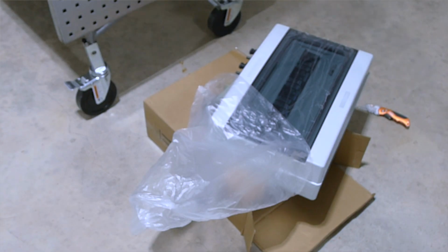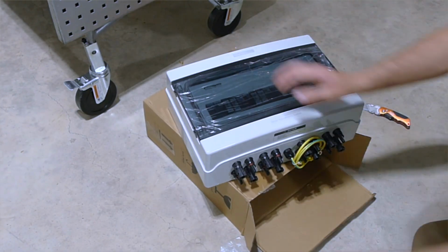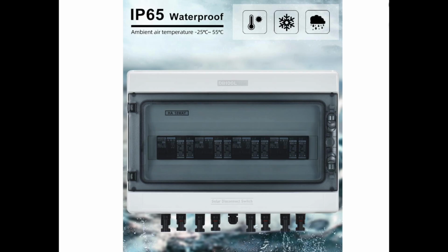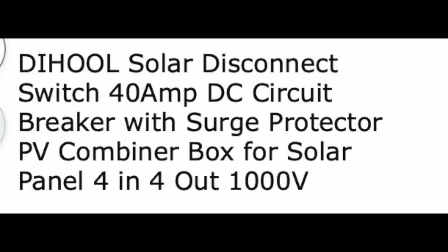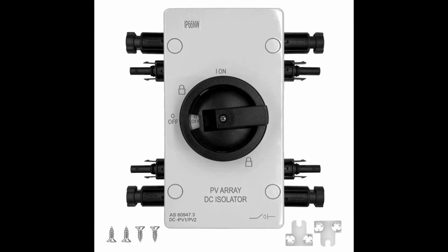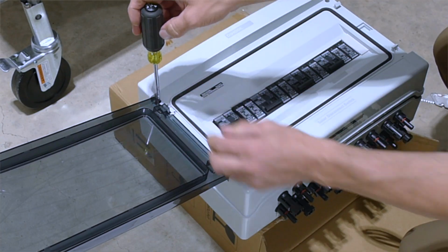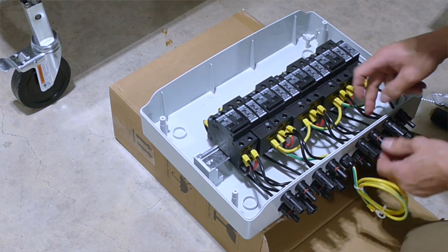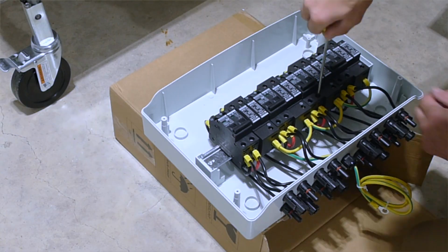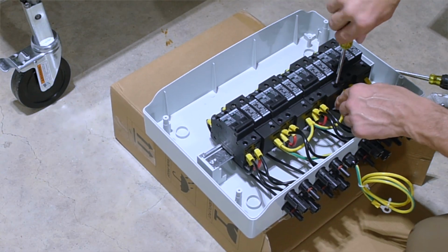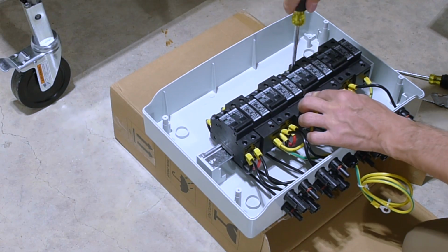Next, we are going to secure this DIHOOL solar disconnect switch, a 40 amp DC circuit breaker with surge protector. This is an IP65 waterproof box with 4 solar disconnect switches, 4 strings in and out, up to 1000 volts DC. We can also use a solar disconnect switch like this without the safety features and turn the DC power off anytime we want to. Since we have to remove the cover to be able to secure the unit on the wall, I just spent some time to secure all the connections before I mount it. If we build a stationary system, we can secure the disconnect either close to the solar panels outside or close to the inverter as well.